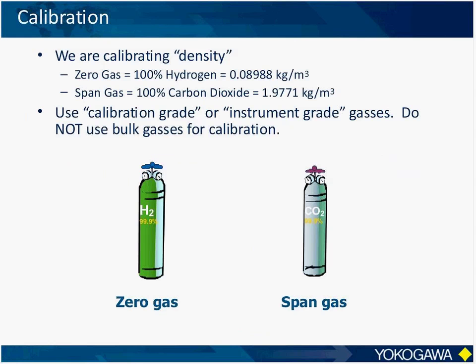Now, calibrations for these applications are performed with two gases, 100% hydrogen and 100% carbon dioxide. And we choose those two because they bracket the full range of densities that the analyzer will measure. Since we are calibrating the density measurement, the very light hydrogen gas is actually the zero calibration gas, and the much heavier carbon dioxide is used as a span calibration gas. And it is recommended for these calibrations that you use instrument or calibration grade gases, not bulk gases. That way we'll ensure the most accurate density measurement possible.